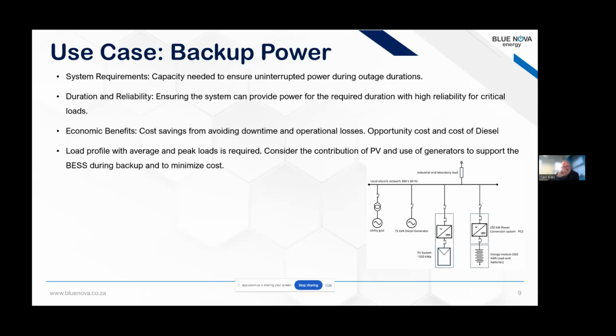As also discussed in the first presentation, if you have PV but the grid goes down and you don't have a battery, you can't use the PV. So by looking at combinations of PV and generators, you can minimize your BESS size to minimize cost, but still have reliable power with cost savings. Just one note - your inverter must be able to handle peak loads and reactive power. As the last question that came up was about, you've got to keep up with the inrush currents, and your inverter must be able to handle that.